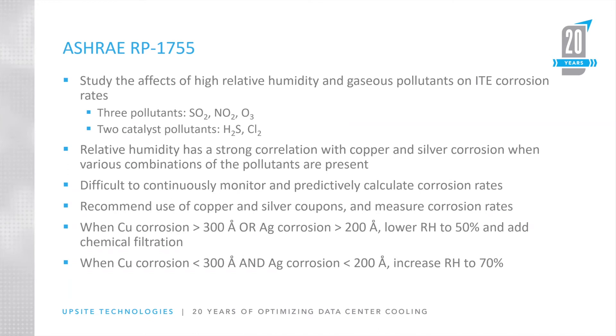The important part is that the facility, if you suspect you might be in one of these high-corrosion activity situations, needs to have the ability to lower the relative humidity down to 50% and keep it at or below 50% to control the corrosion. But you can save some energy and allow your relative humidity to go up if you're not witnessing this kind of corrosion.